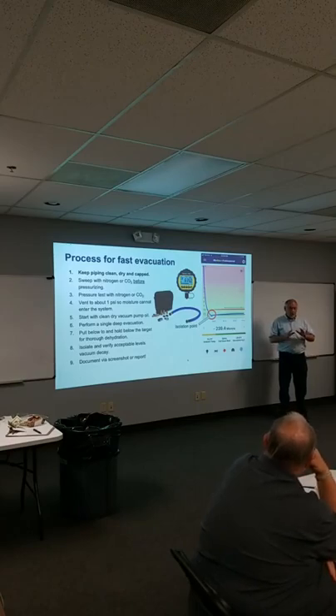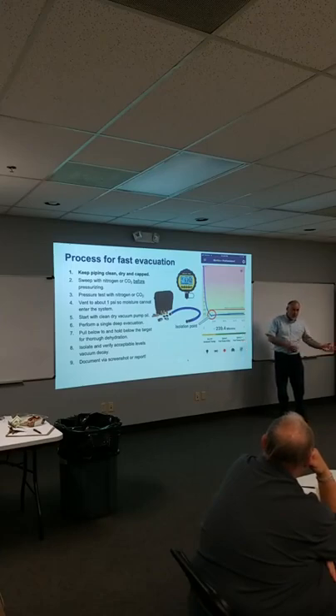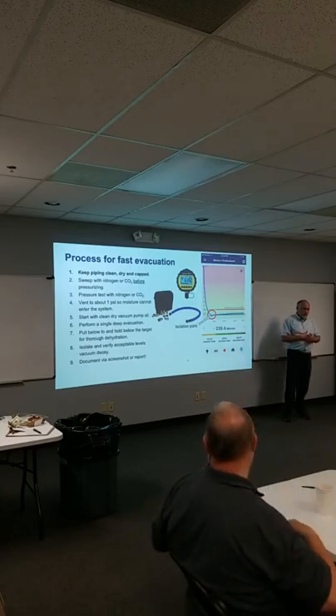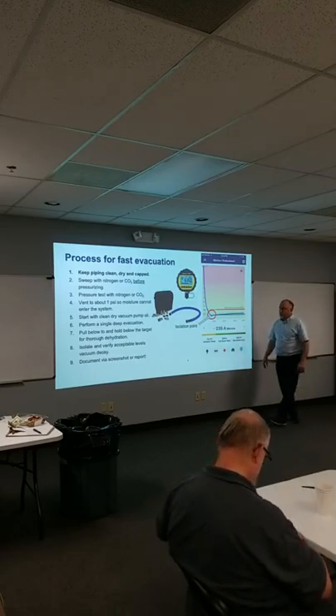And when I say sweep it, I'm talking about less than 20 PSI of nitrogen. Just push the air out of the system. Purge it out for a few minutes. Let all that air get out of there so you've got it replaced with dry nitrogen. And then raise your pressure up and do your pressure test. Okay? You do not want to pressurize it first.